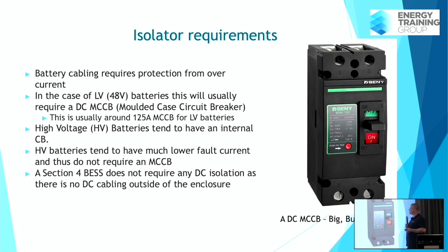A high voltage battery, on the other hand, will usually have a built-in circuit breaker, and when we're looking at cable requirements, you're usually going to run a 6mm square twin to most of your high voltage batteries. Nearly all of your high voltage batteries have a 63 amp circuit breaker built into them. 6mm PV1F DC solar cable is good for around 70 amps. So therefore your 6mm is good to connect to a 63 amp breaker on a battery. But you size your battery cable to the size of the breaker that is inside the battery, all right? That's what dictates your cable size.